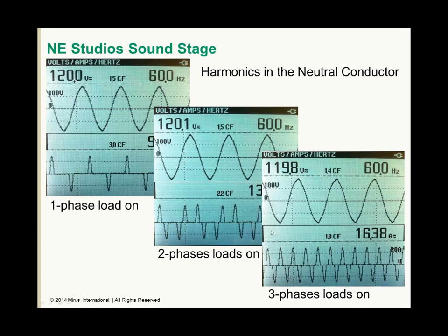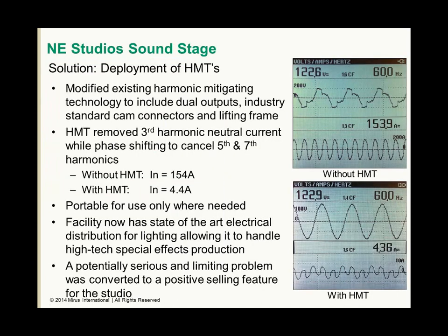It's 180 hertz. So here, in the period that we have one cycle, we end up with 1, 2, 3 cycles on the neutral, or third harmonic. We modified our existing harmonic mitigating transformer technology, the zero sequence filters and phase shifting transformers, to include dual outputs, industry standard cam connectors, and a lifting frame to provide portability and ease of application.